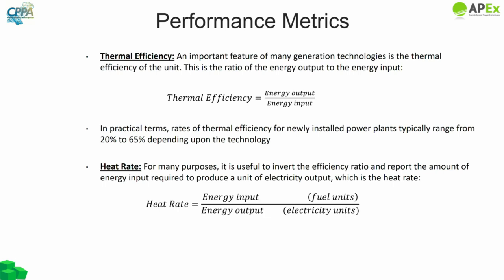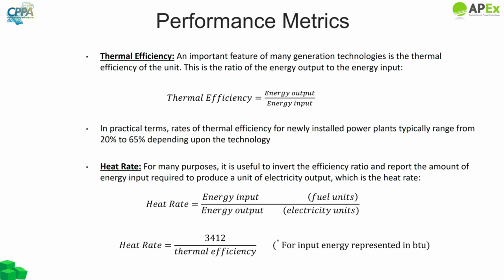We must be careful about the units used when calculating heat rate. While thermal efficiency is unitless, heat rates are reported with different units for energy input and output. In SI units, heat rate is in kilojoules per kilowatt-hour; in some places, kilocalories per kilowatt-hour; and in the US where British imperial units are used, BTUs per kilowatt-hour. To translate from thermal efficiency to heat rate, we invert the ratio and multiply by the appropriate conversion factor. For BTU systems, this factor is 3,412, so heat rate equals 3,412 divided by thermal efficiency.